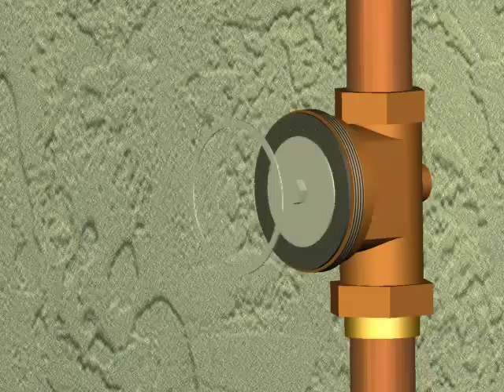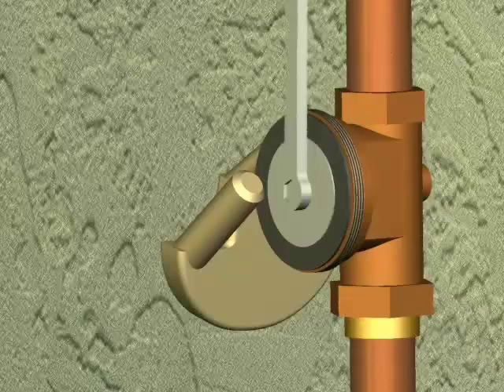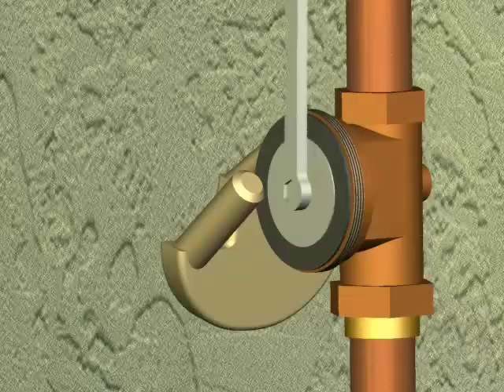If the valve is installed vertically, the parts may fall out of the bell when it is removed. You will want to hold the diaphragm against the edge of the body to keep it from rotating. Unscrew the bolt in the center of the diaphragm and remove the diaphragm disc and the diaphragm.